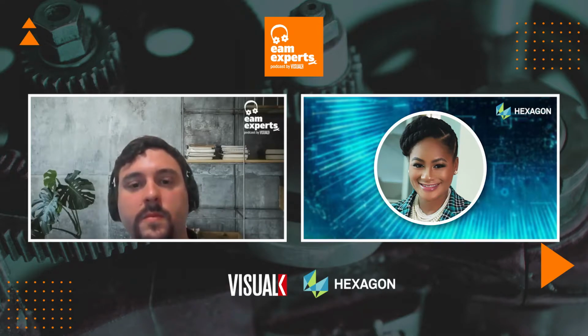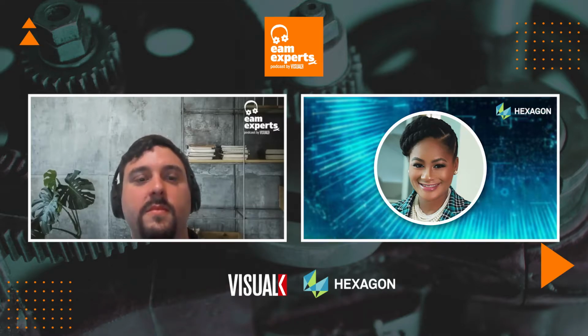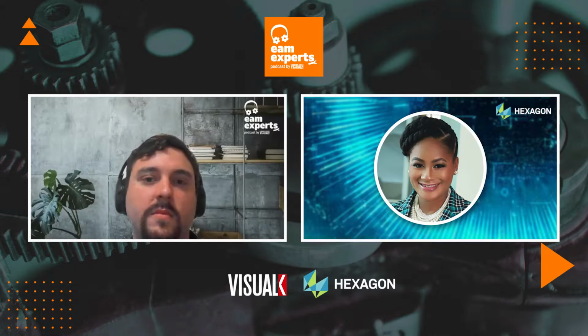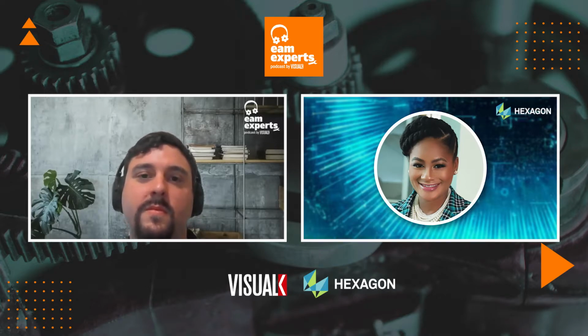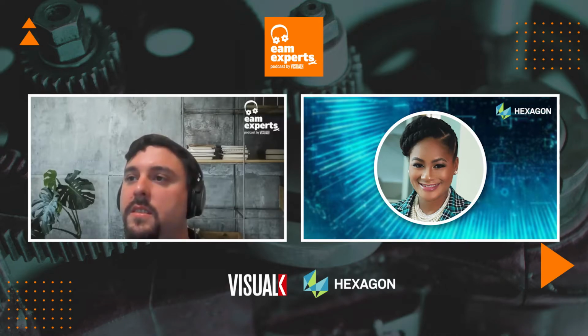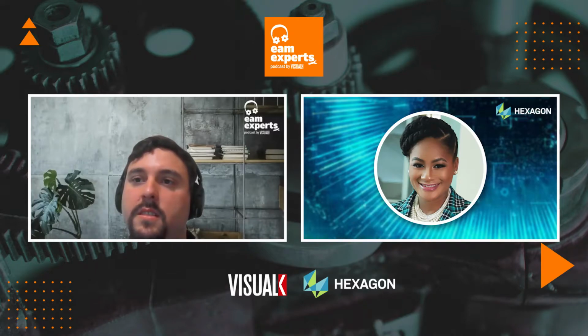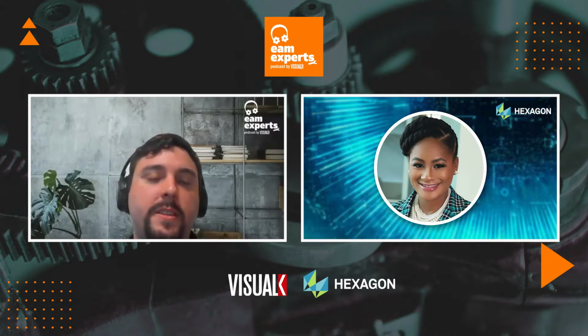So to finally answer your question, it's a lot of things. I've gone through a couple of different levels and talked about a couple of different types of equipment, but it's everything from level 0 being the field instrumentation, level 1 being the basic control systems, and then level 2, where we're getting into the operator interface level, where the operators are actually using equipment to monitor and control different systems. Exactly. Then level 3, those are devices that are used to share and send information across the plant. Right, and then you break it back to IT.